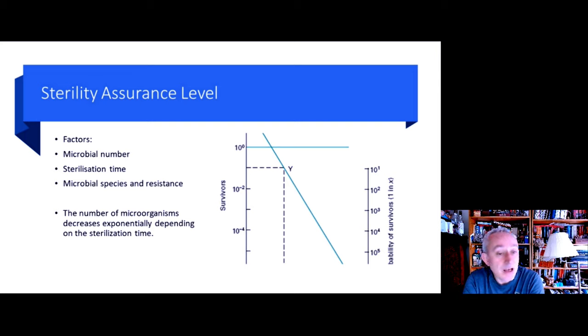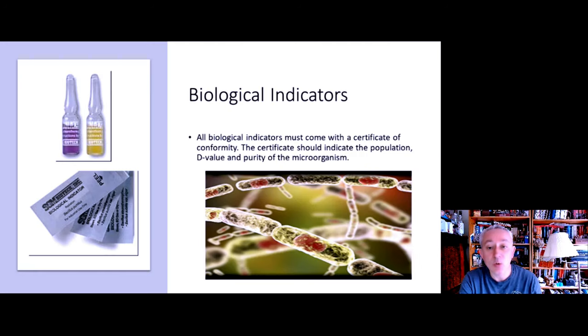So in essence, the hotter the temperature and the longer the time, then the faster the kill rate. And we require a particular temperature and a particular time to get the optimal kill rate. So how do we know all of this? Well, we need to use biological indicators.